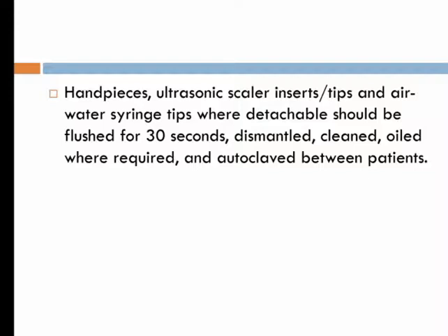Handpieces, ultrasonic scaler inserts or tips, and air syringe tips, where detachable, should be flushed for 30 seconds, dismantled, cleaned, oiled where required, and autoclaved between patients. Handpieces left overnight should be allowed to discharge water for 2 minutes at the end and beginning of the day.